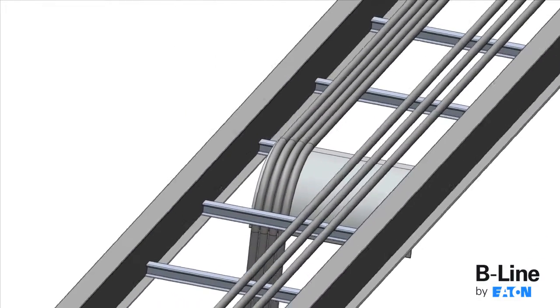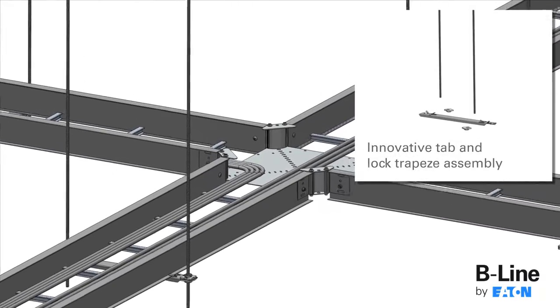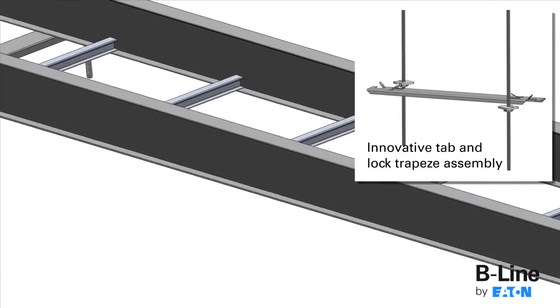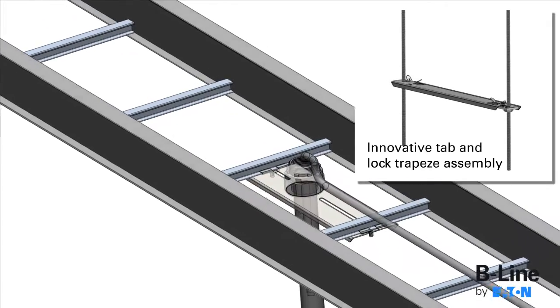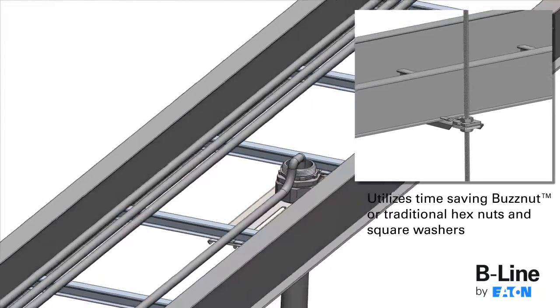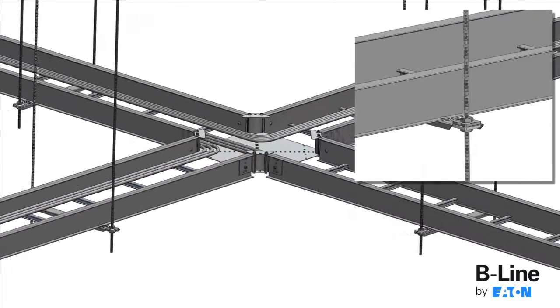The QuickSplice System also includes a full line of labor-saving accessories, including the innovative tab-and-lock trapeze assembly, which eliminates the need for hold-down clamps on the cable tray system. By simply using a flat-head screwdriver, the installer can position and lock the trapeze onto the threaded rod and clamp the cable tray to the support assembly.